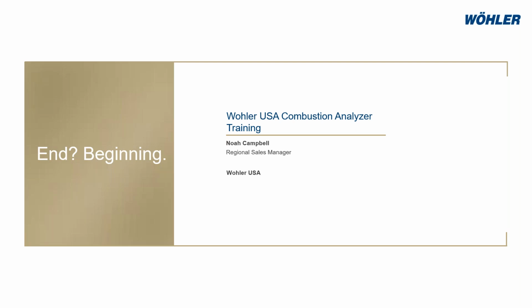So your question is about using the manifold inlet pressure, using the built-in manometer of the analyzer. The A450 and A550 have a built-in manometer, so you'll be able to see the draft readings when you do a combustion analysis test, and that parameter is identified by PR. Depending on what analyzer you have, there's a negative and a positive draft port on the bottom of the analyzer. You can change your hoses over to one port or the other to give you a negative draft or a positive draft. I'm hoping that answers your question.